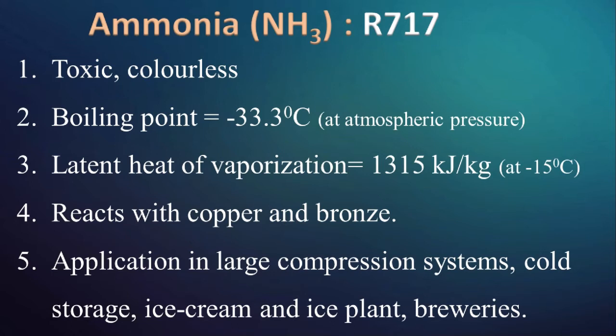To evaporate heat in the evaporator around minus 15 degree Celsius, we need to maintain higher pressure in the evaporator, so the compressor suction will not be in vacuum. It helps to improve the operating capacity of the compressor. Latent heat of vaporization of ammonia is 1315 kJ/kg at evaporation temperature of minus 15 degree Celsius. When ammonia is mixed with air, it is flammable and explosive. Leak detection of ammonia can be done by using a burning sulfur candle, which forms white ammonium sulfite fumes.